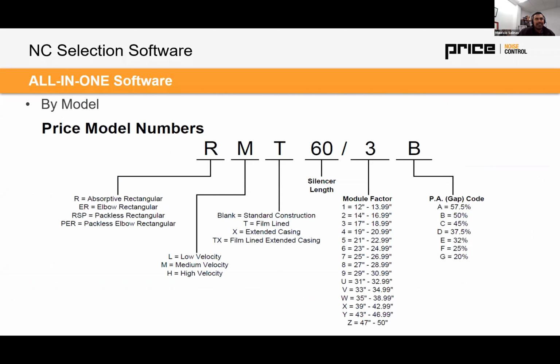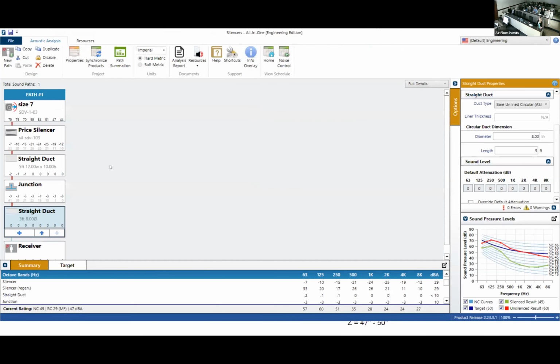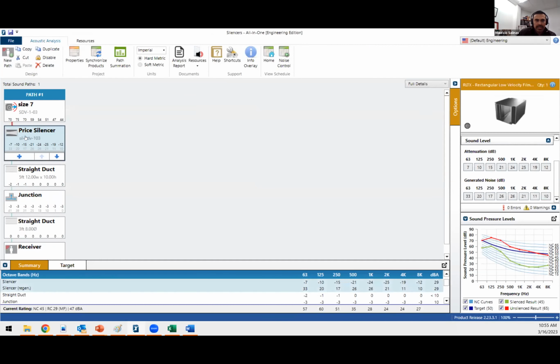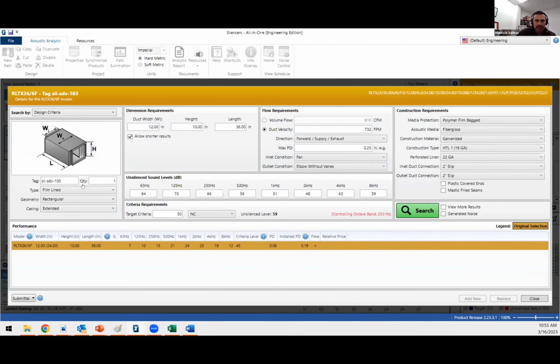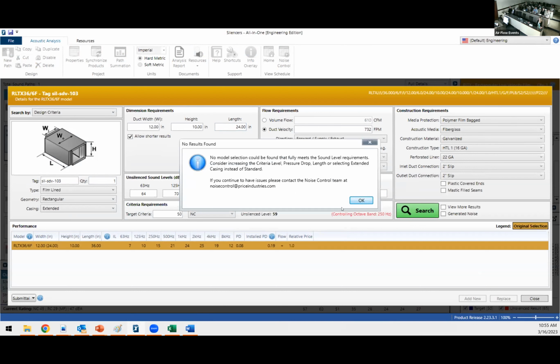Yes, question. There is one, hang on. So I was picking a silencer and are there any limitations on the dimension requirements when you pick an extended casing? Yes, there are some, and the software typically guides you. For example, if you're doing an extended casing, your minimum length has to be 36 inches. You cannot do a 24 inch. So if you try, it won't let you.